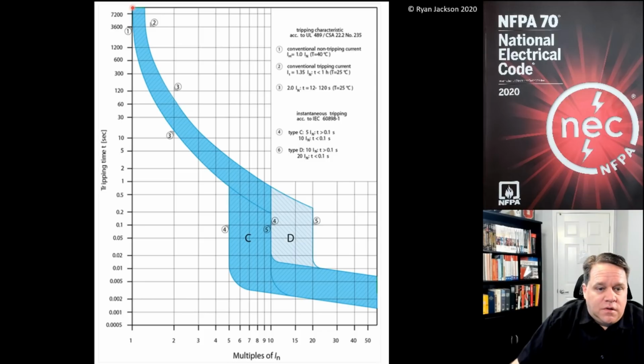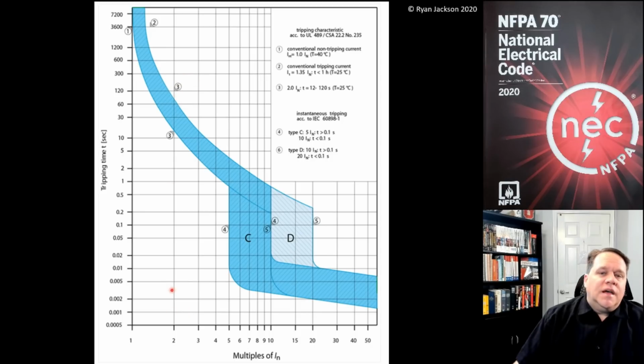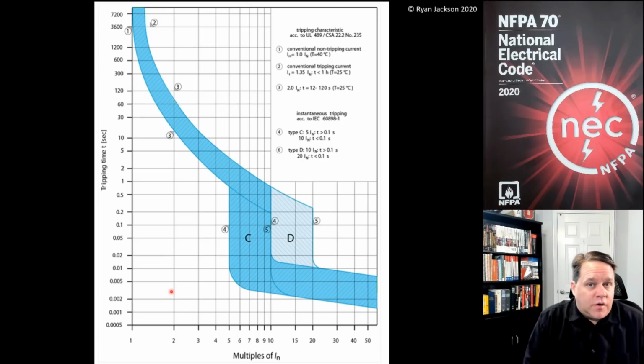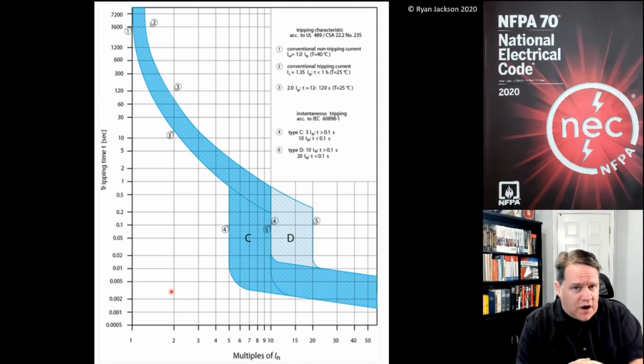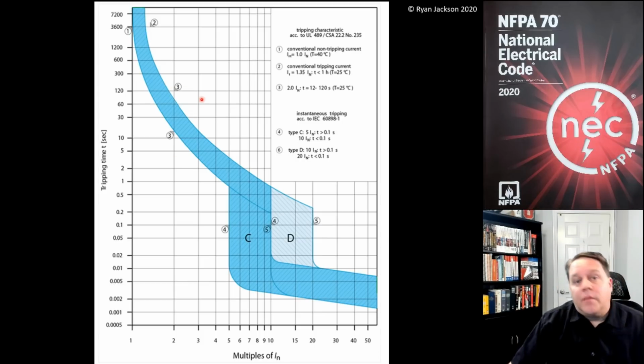It's rated 20 amps. If I put 2 times the rating, or 40 amps, how fast will 40 amps on a 20 amp circuit breaker open? If I follow this up, and these are all going to vary based on the breaker, it will open somewhere between 15 seconds and 2 minutes, give or take. That's at 40 amps. Now, is that good enough if I have a ground fault? If I have that metal lighting pole for my parking lot light, if it is energized to a ground fault, should that remain energized for up to 2 minutes? Probably not. I think we can all agree that we need the breaker to trip faster than that.